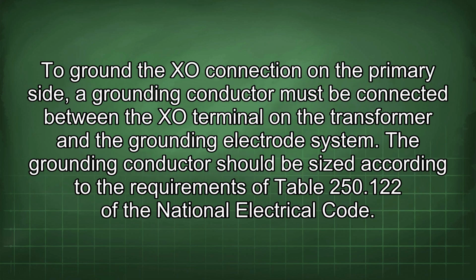To ground the X0 connection on the primary side, a grounding conductor must be connected between the X0 terminal on the transformer and the grounding electrode system. The grounding conductor should be sized according to the requirements of Table 250.122 of the National Electrical Code.